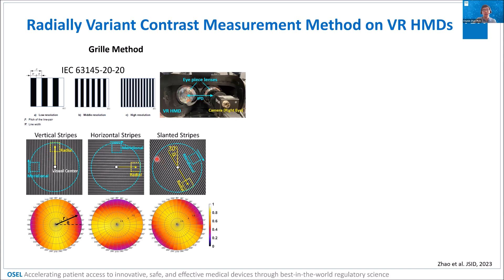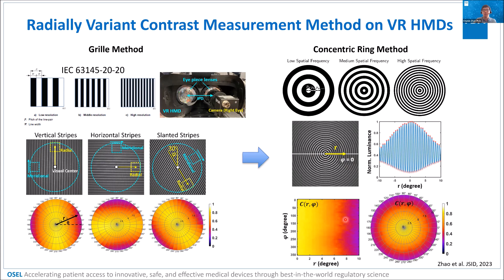So at OSEL, we developed this concentric ring method that is similar to the grill method, but using this bullseye pattern with periodic black and white rings. And you can also measure it at different spatial frequencies to measure the contrast. You load the pattern and get the luminance profile, and you measure the contrast, the modulation contrast, as a function of the radius and the rotation angle. You can get a polar plot as shown here. And so you can see this pattern can capture the contrast degradation, the spatial variation of the contrast, much better than the grill pattern. So that's one example of the test method we developed here at OSEL.